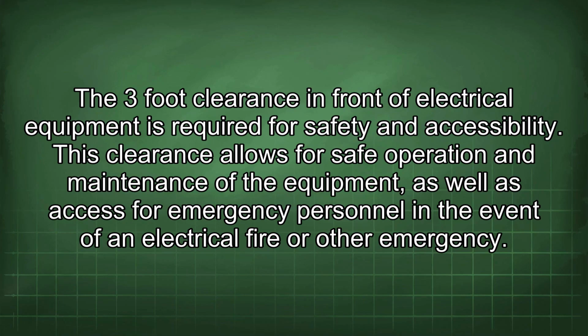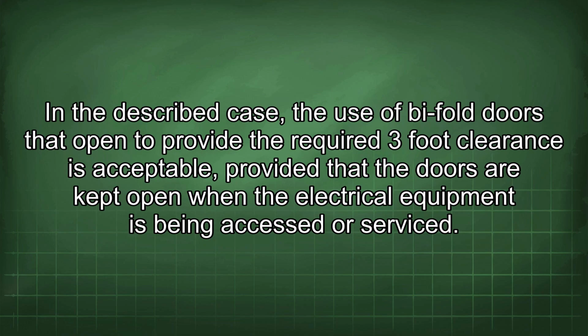3-foot clearance in front of electrical equipment is required for safety and accessibility. This clearance allows for safe operation and maintenance of the equipment, as well as access for emergency personnel in the event of an electrical fire or other emergency. In the described case, the use of bifold doors that open to provide the required 3-foot clearance is acceptable, provided that the doors are kept open when the electrical equipment is being accessed or serviced.